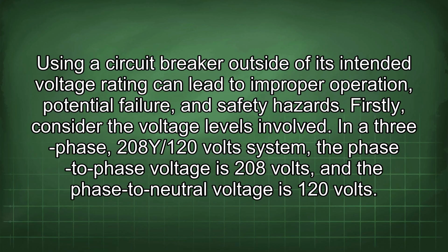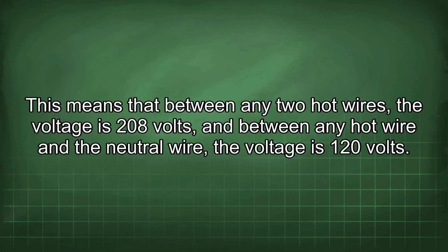Firstly, consider the voltage levels involved. In a 3-phase 208Y/120 volts system, the phase-to-phase voltage is 208 volts, and the phase-to-neutral voltage is 120 volts. This means that between any two hot wires, the voltage is 208 volts, and between any hot wire and the neutral wire, the voltage is 120 volts.